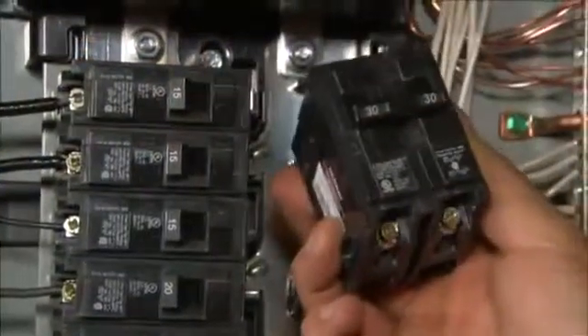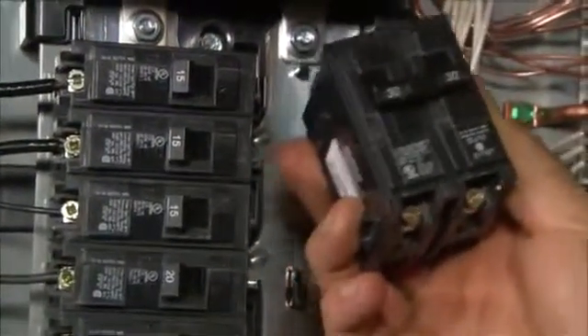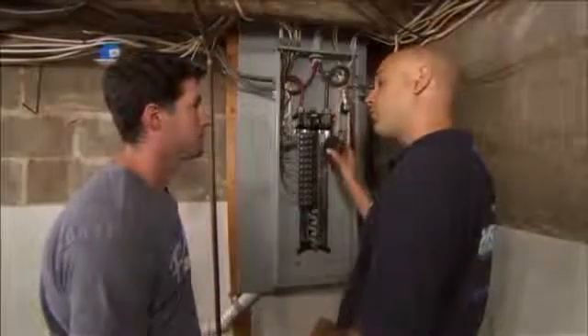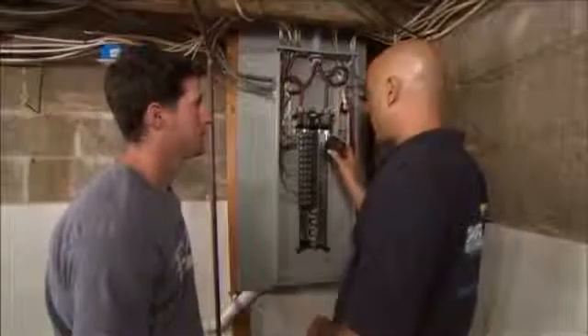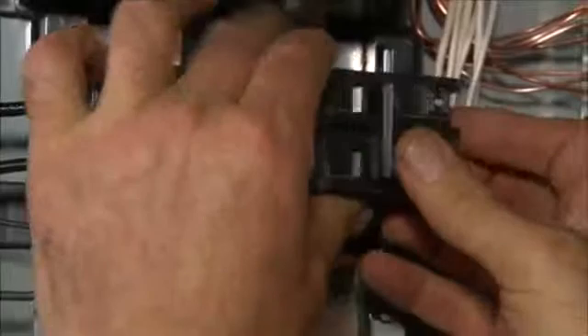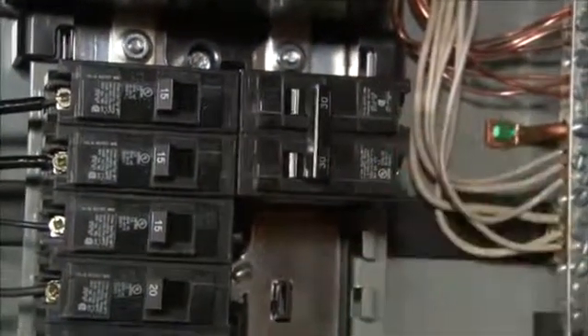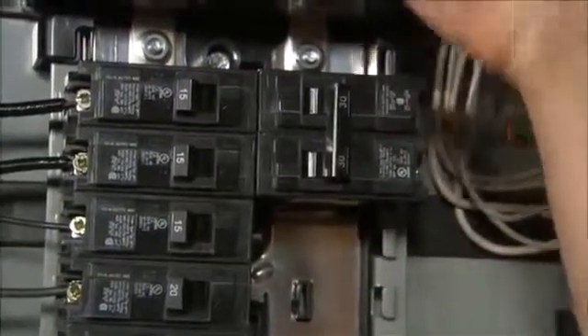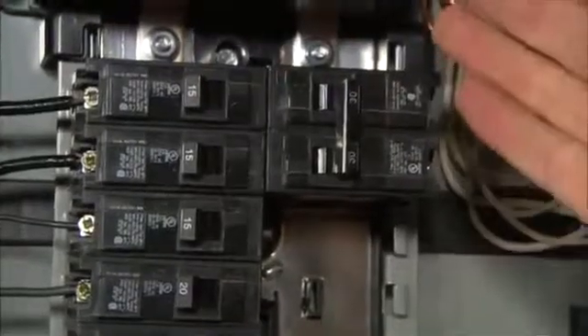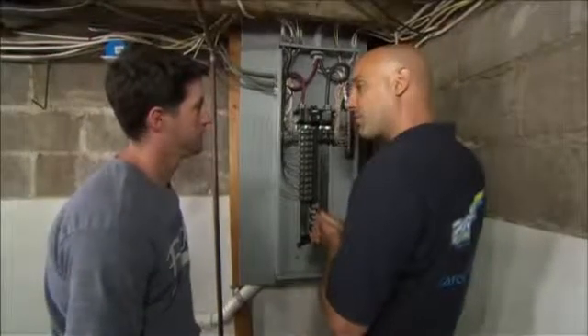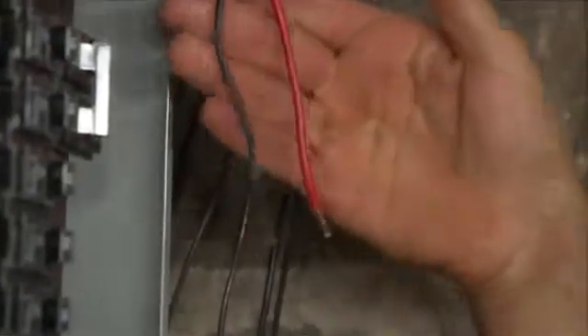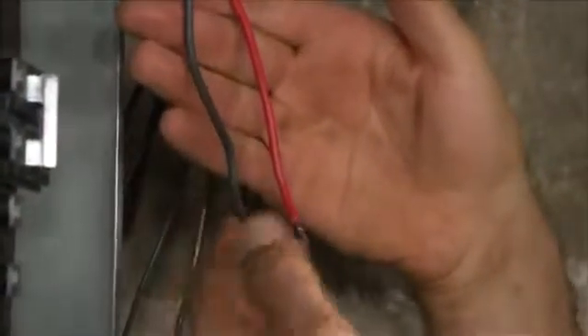This 30 amp circuit breaker is a little different. It's a 2-pole circuit breaker. It provides 240 volts to your electric clothes dryer. So what I'm going to do is snap this in. Now it's installed. It gets 120 volts from the left side of the panel and 120 volts from the right side of the panel, giving the clothes dryer 240 volts of electricity. Now instead of just one wire, there are 2. We have a black wire and a red wire.